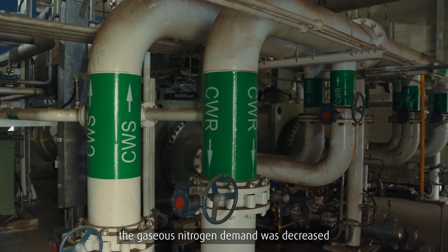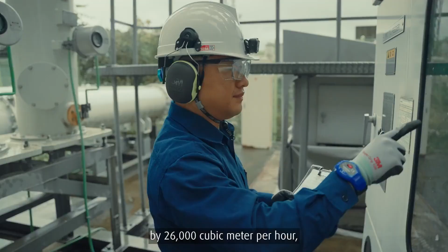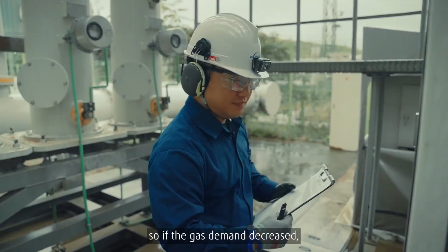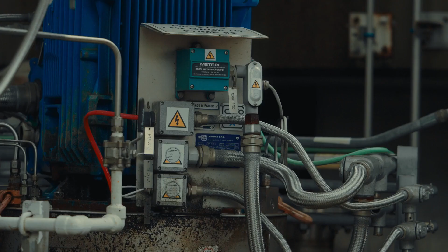In the recent 2 years, the gaseous nitrogen demand decreased by 26,000 cubic meters per hour. So if the gas demand decreases, the produced nitrogen and oxygen have to be vented out. It means we had to raise some of the power cost. We had to turn down the plant, but there is a limit to turning down, so we decided to turn off one of the MACs during the winter time.